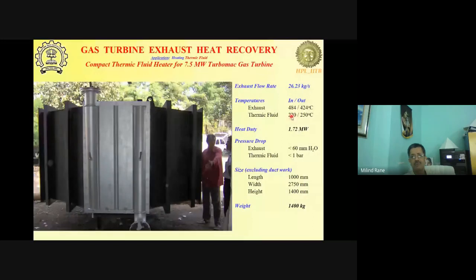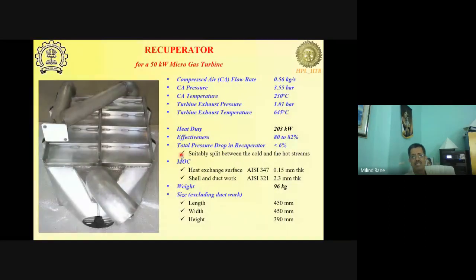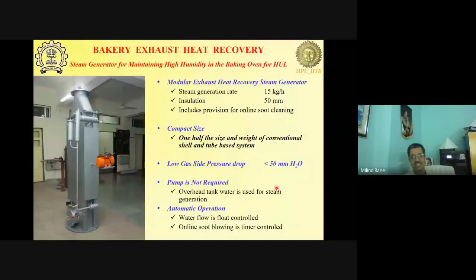You can see here 220 to 250 degrees centigrade. The heat recovery in this particular example was 1.7, and our heat exchanger was 1/3 the size of the conventional unit. There is a micro gas turbine recuperator. The challenge was to keep this below 200 kg. Then the next limit, they reduced it to 120 kg. We delivered at 96 kg for the first unit. This was the import substitute.